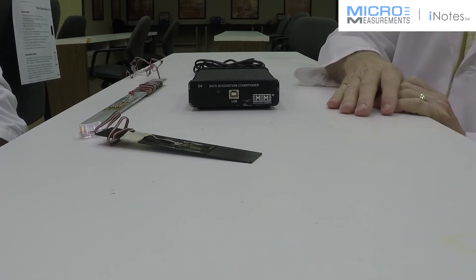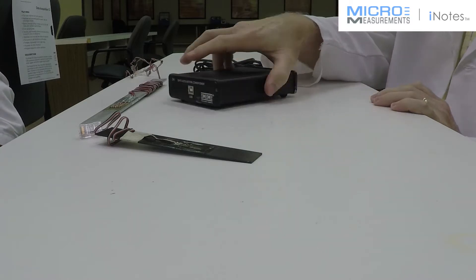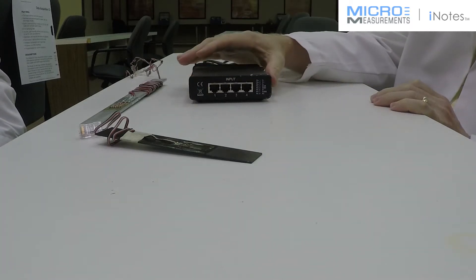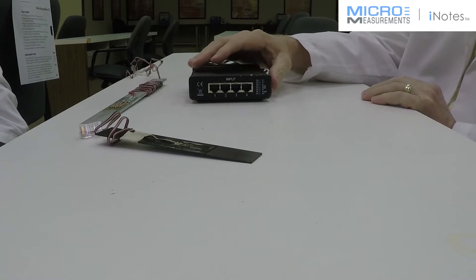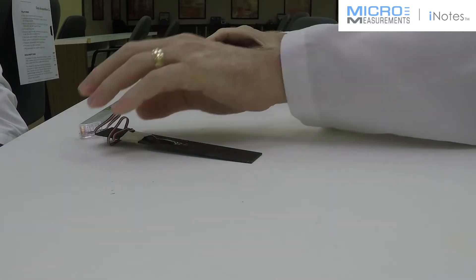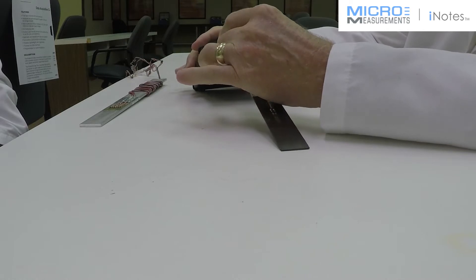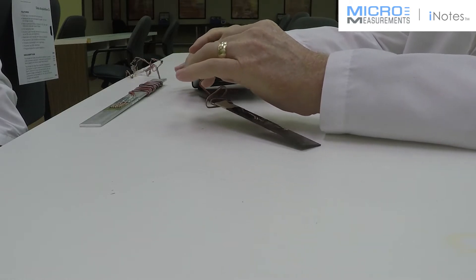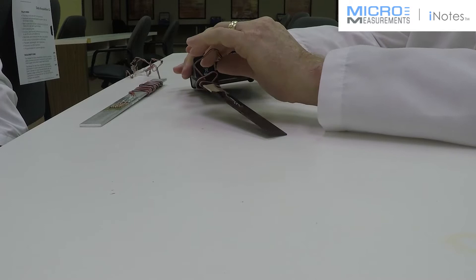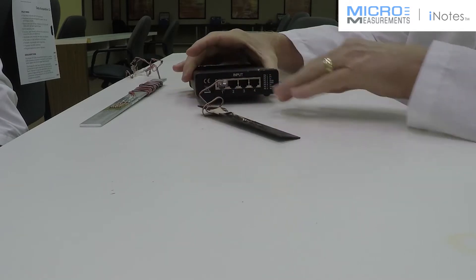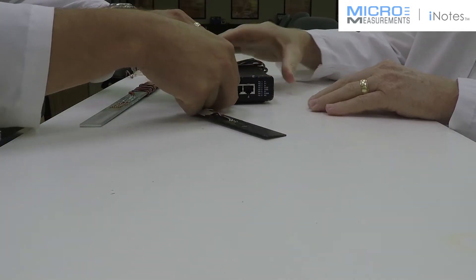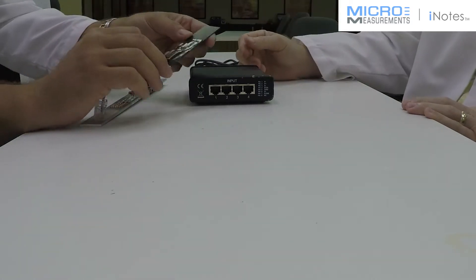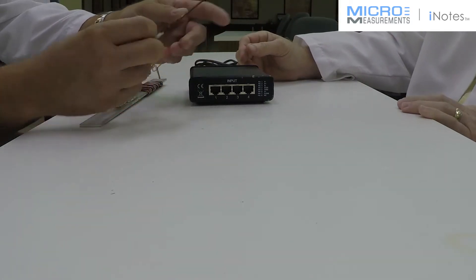It allows you to connect strain gauges or strain gauge-based transducers simply with an RJ45 connector. You can plug in quarter-bridge, half-bridge, or full-bridge circuits into this just with the click-on RJ45. Even strain gauges that are glued onto a composite? Right, like this one.